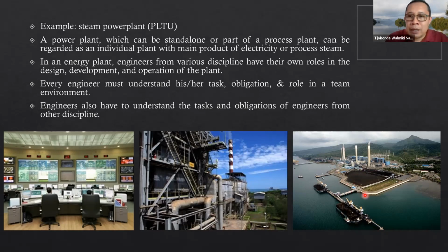But you cannot just leave it like that for weeks on end and not expect that there's any fire inside it. Again, coal is quite a dangerous substance if you keep it in a large quantity. So in order to avoid bara api, in order to avoid spontaneous fire, every certain period of time this pile of coal needs to be turned over.